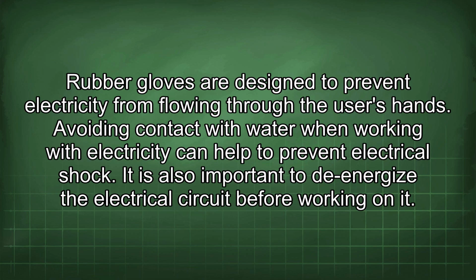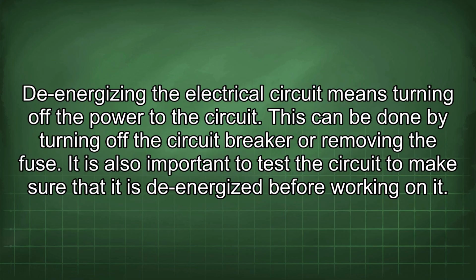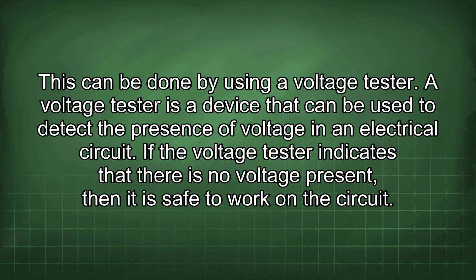It is also important to de-energize the electrical circuit before working on it. De-energizing the electrical circuit means turning off the power to the circuit. This can be done by turning off the circuit breaker or removing the fuse. It is also important to test the circuit to make sure that it is de-energized before working on it. This can be done by using a voltage tester. A voltage tester is a device that can be used to detect the presence of voltage in an electrical circuit. If the voltage tester indicates that there is no voltage present, then it is safe to work on the circuit.